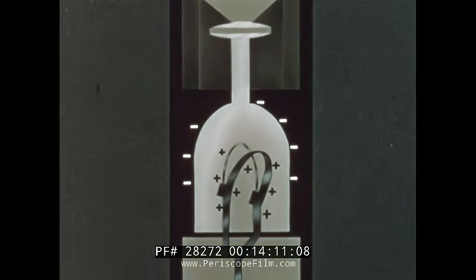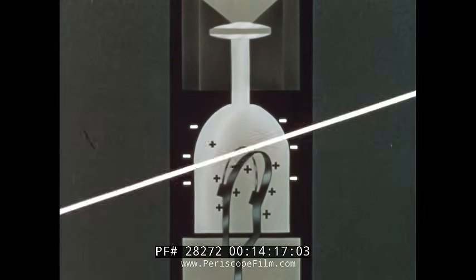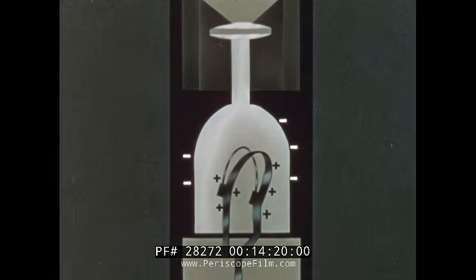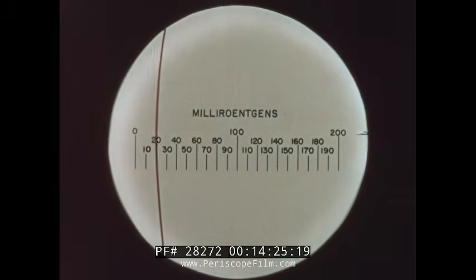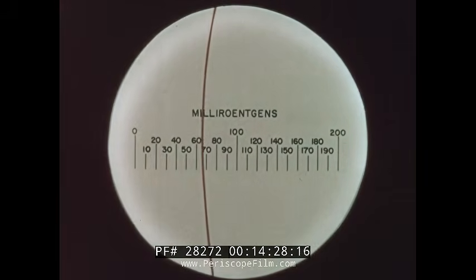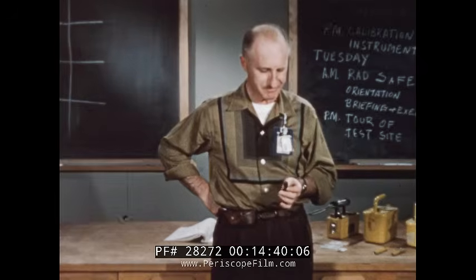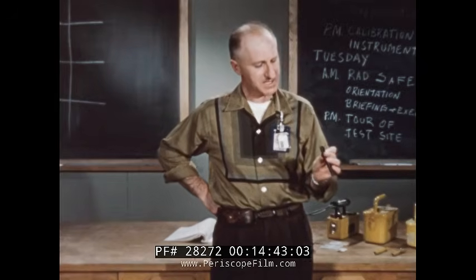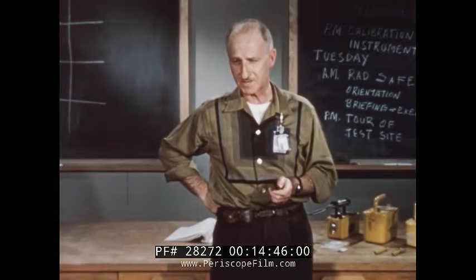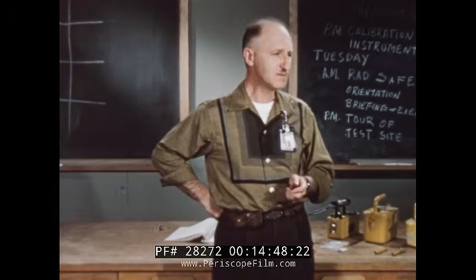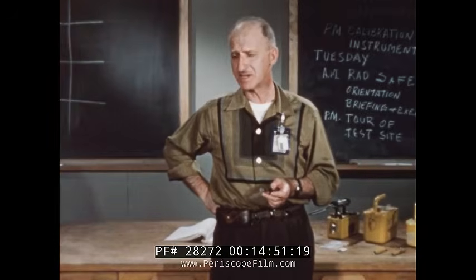When exposed to radiation, the air in the chamber surrounding the fiber is ionized and ion pairs are formed. This decreases the charge and allows the fiber to again approach the plate. By holding the dosimeter up to the light, the fiber can be seen in relation to the scale. The position of the fiber on the scale corresponds to the amount of radiation to which the instrument has been exposed. The operation of this type of dosimeter is like that of a voltmeter, the decreased voltage being converted and indicated as an increase in the absorbed radiation.